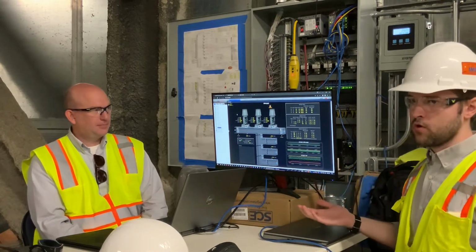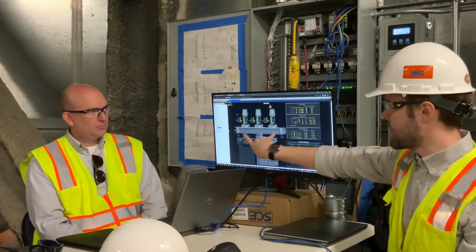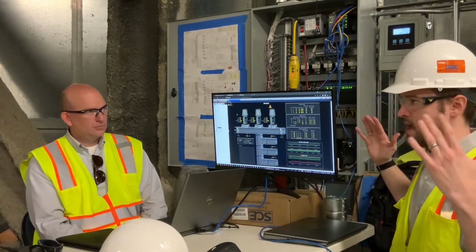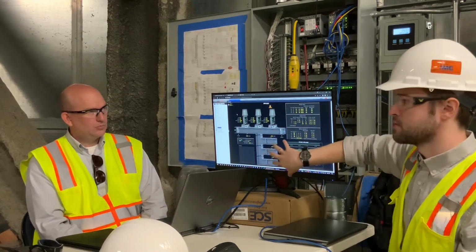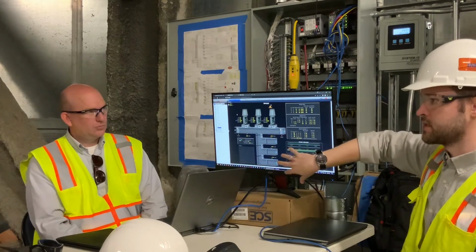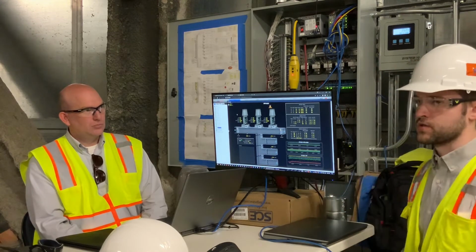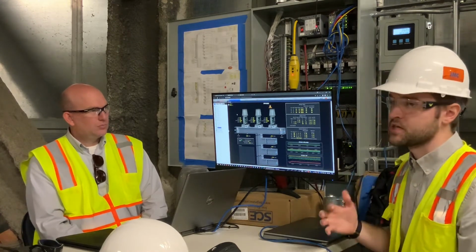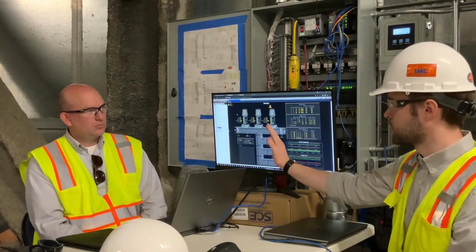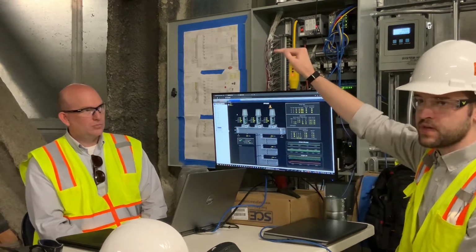The pressure control is done primarily by your bypass dampers here. All that does is, as pressure gets below set point, so you have too much suction in your duct, bypass dampers will open and just allow outside air to cycle through those exhaust fans up and out. If your pressure is not sufficient and your dampers are fully closed, then your fans will increase speed.